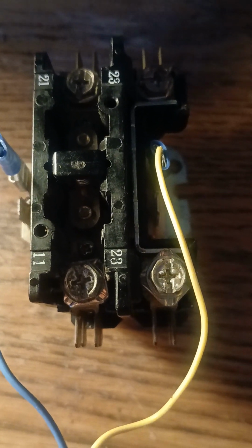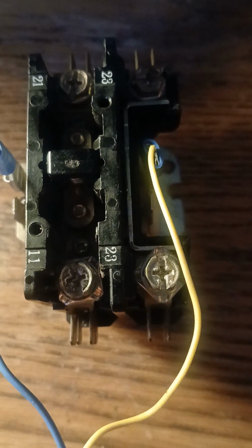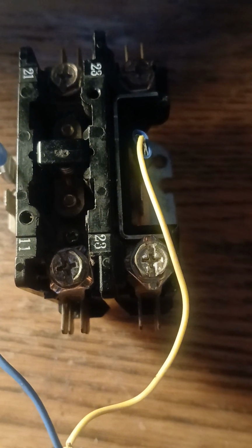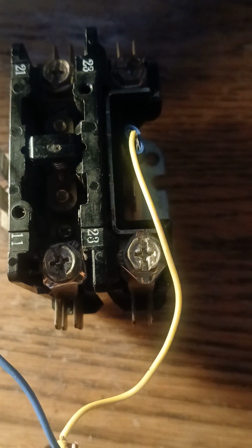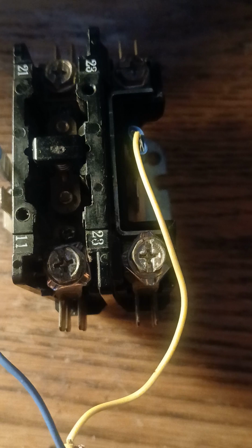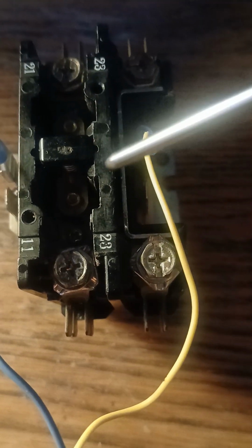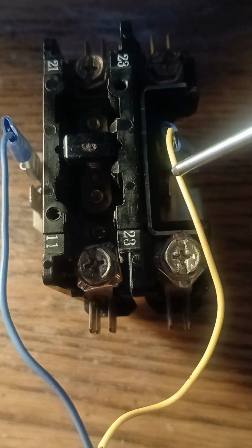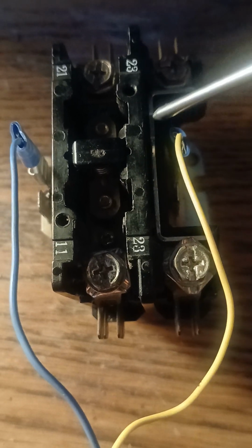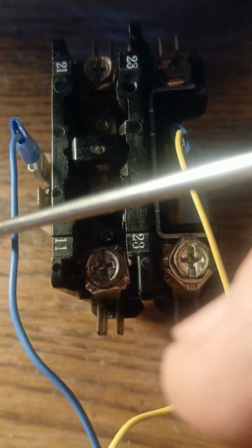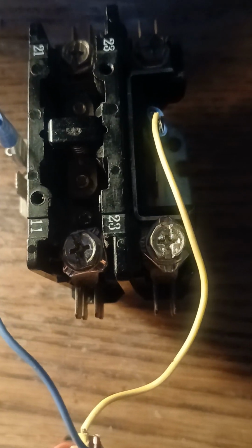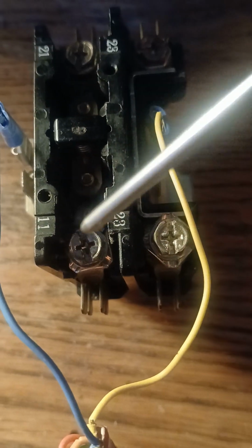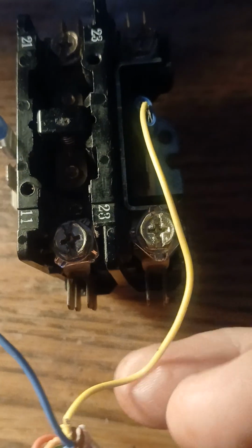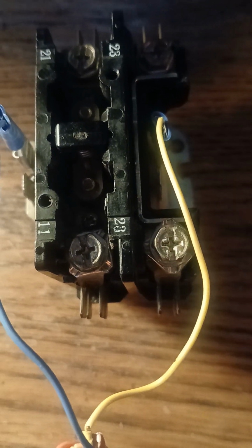So if the thermostat called for cooling and the set temperature got to a certain degree at this point, and then it clicked on, I'm thinking the red wire in the thermostat would power up the yellow wire, it would send power. So this would send power out, and again, it's just a hot and a common. So the yellow wire would be hot. But if you do see a red wire coming out here, or if you see two yellow wires hanging off or whatever, and then this could be pigtailed onto it somewhere, don't be alarmed.